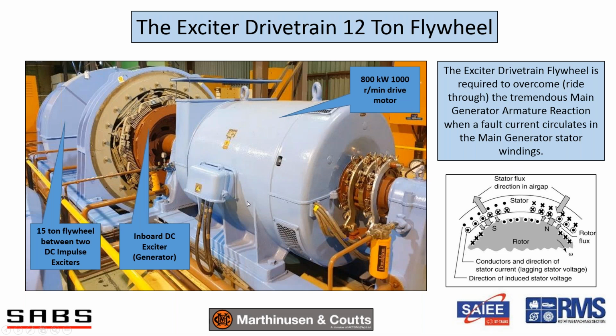Here's the drive motor, 800 kilowatt, 1000 RPM, 6.6 kV, also started via a liquid resistor starter. Then this is the inboard DC exciter here, and on the other end is another exciter for the other generator, and then here is the flywheel. It's covered by a guard for obvious reasons. And why do you need a flywheel? Well, the generators are flywheels in themselves because the rotors have very high inertia.